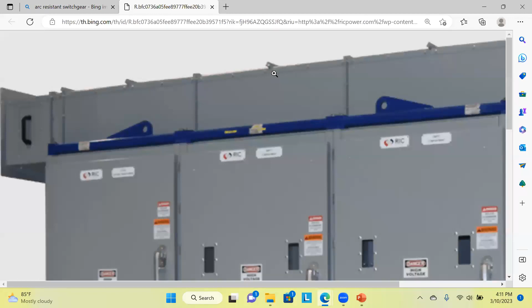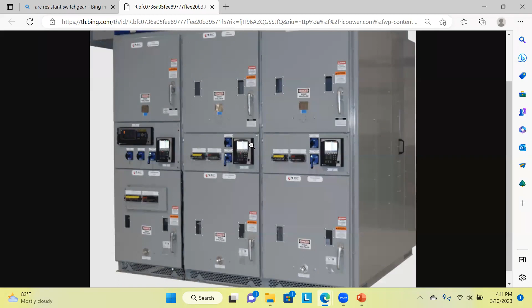In the metal clad switchgear, you won't find this chimney at the top, which has a direction at the back. So if a person is working in front of it performing a switching operation, and there is a flashover, the incident energy will be directed towards him. That is basically a normal metal clad switchgear.